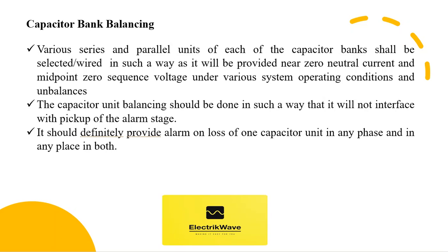Capacitor bank balancing shall be done in such a way that it will not interfere with pickup of the alarm stage. However, it should definitely provide alarm on loss of one capacitor unit in any phase and in any place in both set 1 and set 2. It can be proved by getting actual site measurement of the system voltages for R, Y and B phases for a fairly good period to get the extent and trend of the system unbalances present at site. The capacitor unit balancing should be done accordingly.